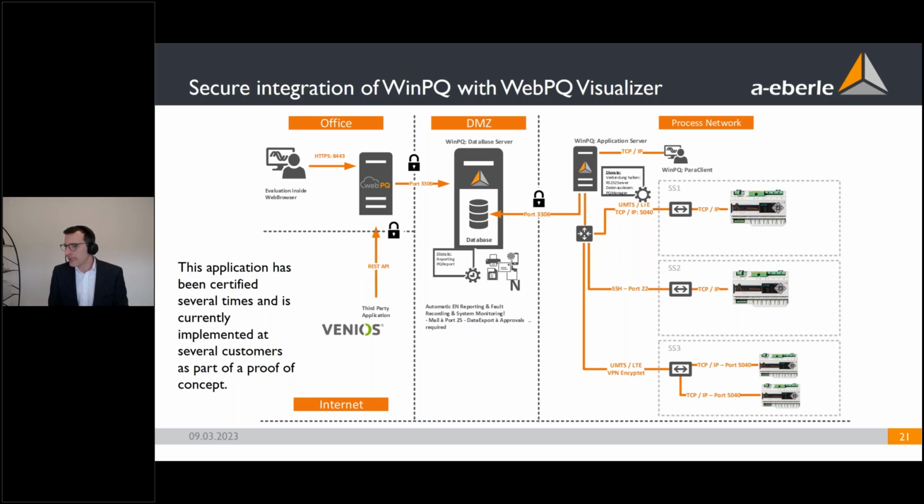How powerful must the connection between the local instrument and the cloud be to bring such a large quantity of data? If a GSM connection is necessary, how much data must be contracted with the SIM? This is a really good and understandable question. The point is, we don't need a very high data rate. Such a meter transfers only about 20 megabytes of data per week into this database, in a medium average calculation.